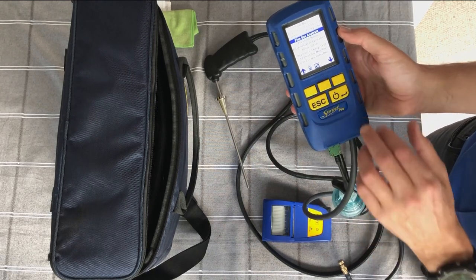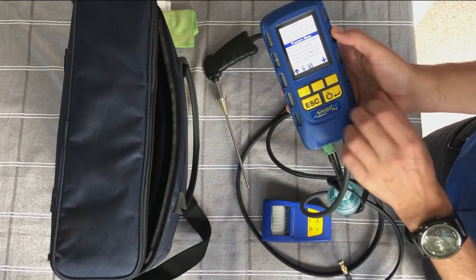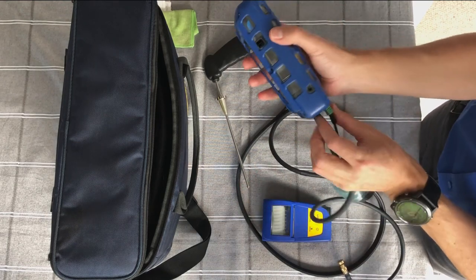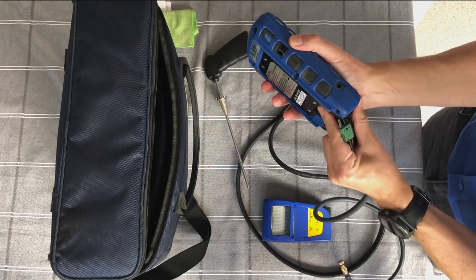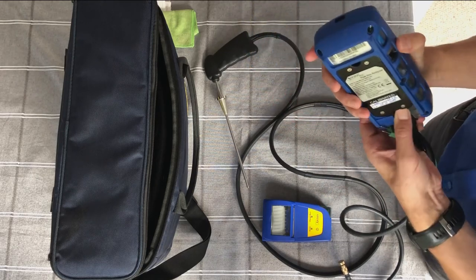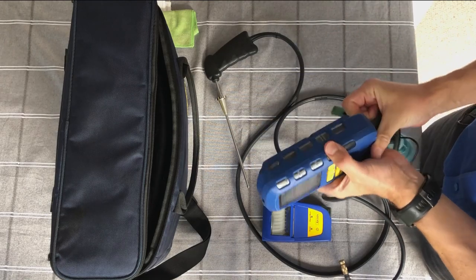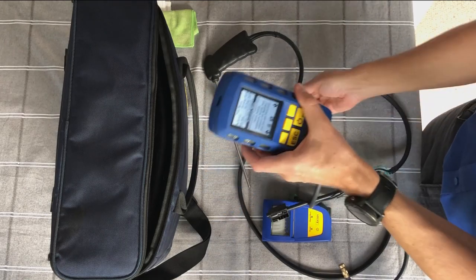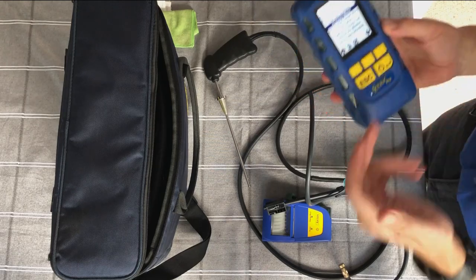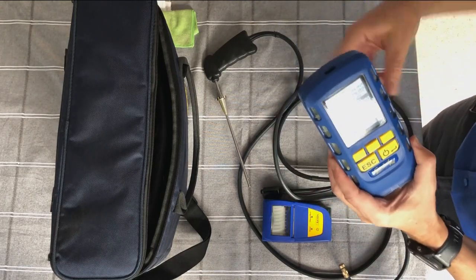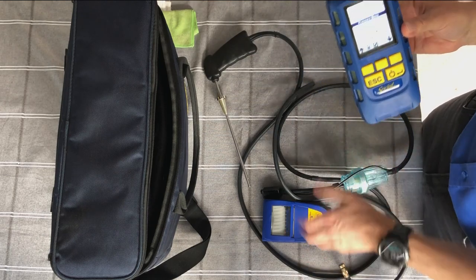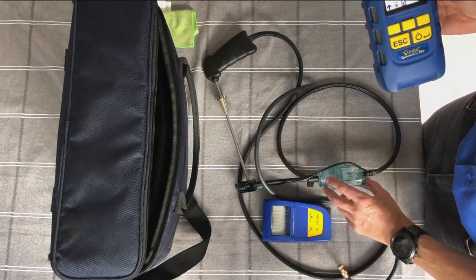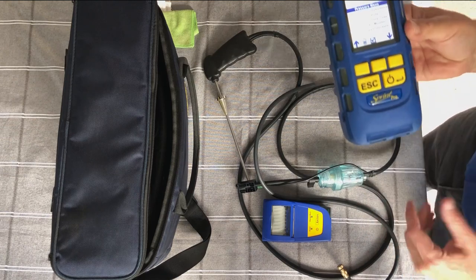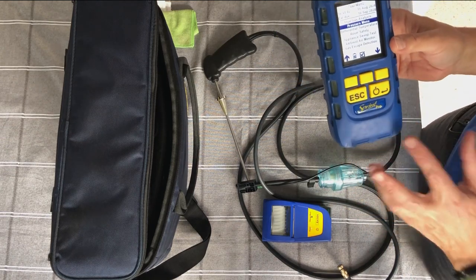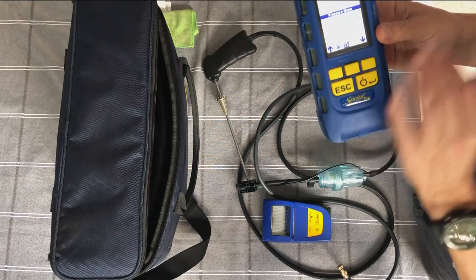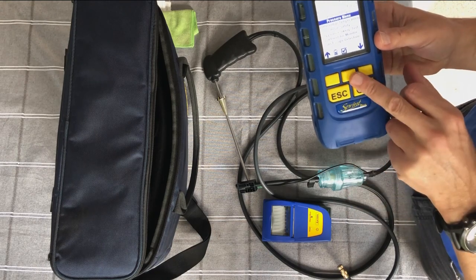Yeah, that's gone a bit quieter again, that's good. All right, so again, next mode down is pressure mode. So I'm not using flue gas now, so I can detach this. What I would recommend is when you turn it off normally, you want to be turning it off with the flue probe attached, because it does another purge on shutdown. It's only 10 seconds, but it might take any excess flue gases out of the probe. So always worth having the flue probe attached when you turn the instrument off. But for the demonstration, I'm going to run through this without it attached.